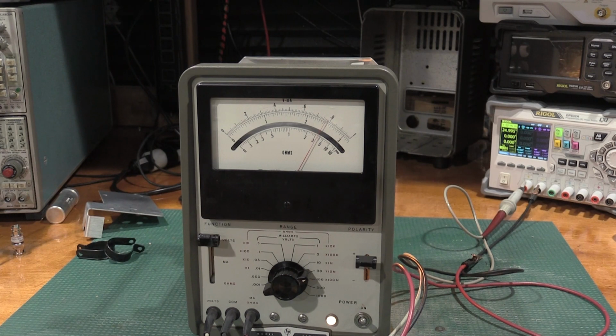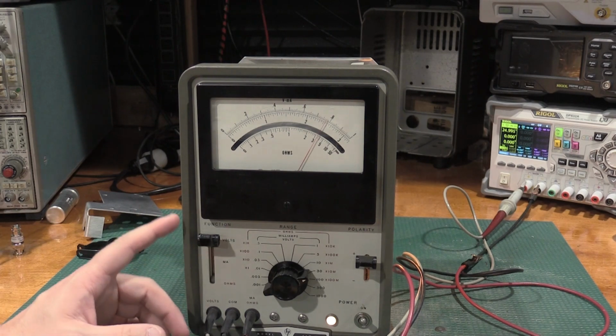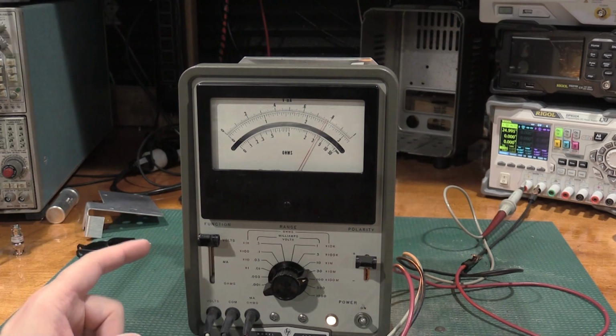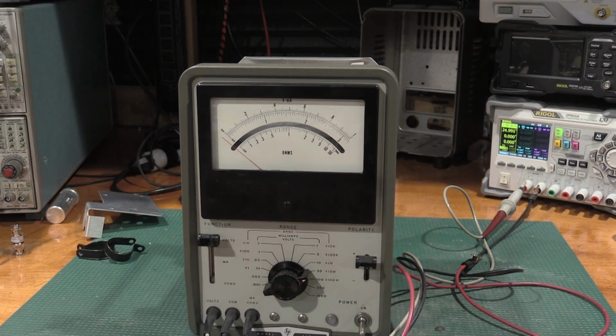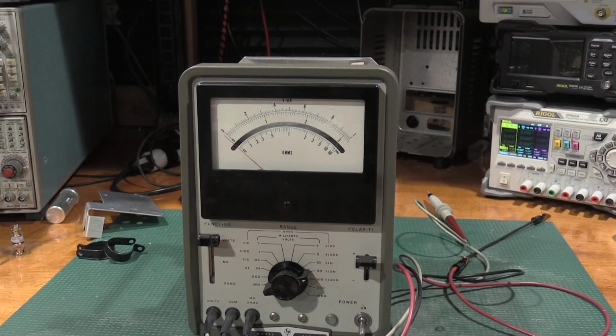I was pretty confident that this was going to go relatively smoothly, so I've got the 7510 warming up and the 343 warming up. So I'm going to turn this on and let it warm up for as long as they do, because this needs, I think, a 30-ish minute warm-up time. They need an hour and a half, both. So I do not need to use the 5200A because this is not an AC meter. This is only volts, milliamps, and ohms. But we'll let everything warm up. Turn this off for now, so I can put the shields back on without getting shocked, and then it's just a waiting game.